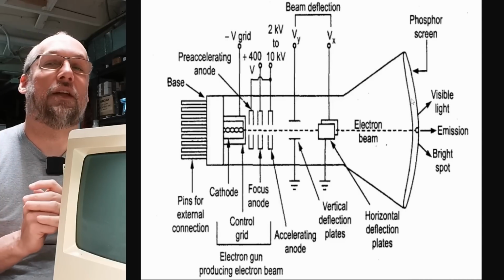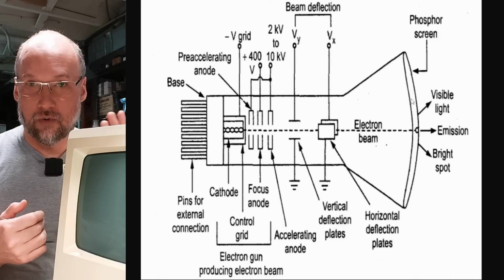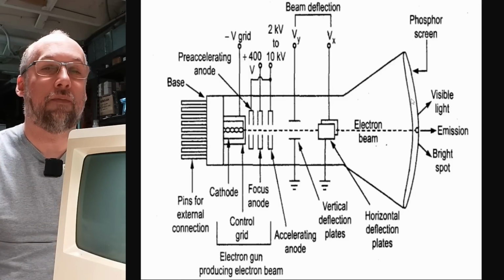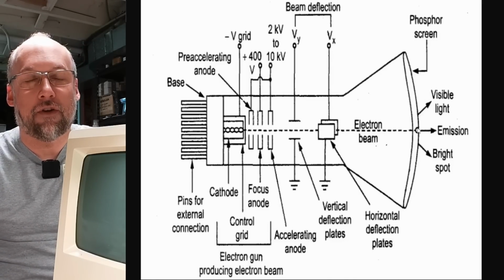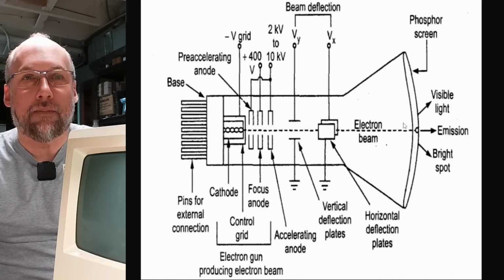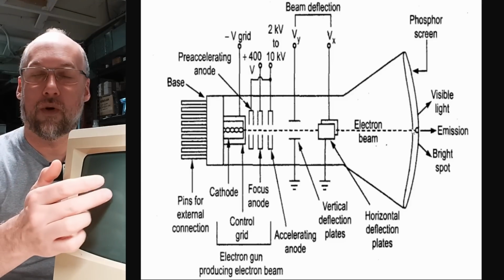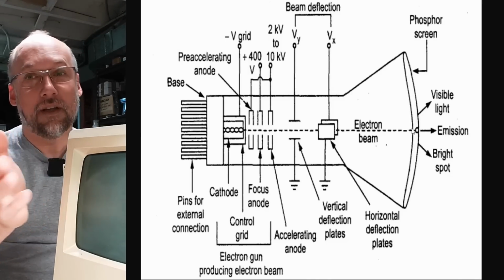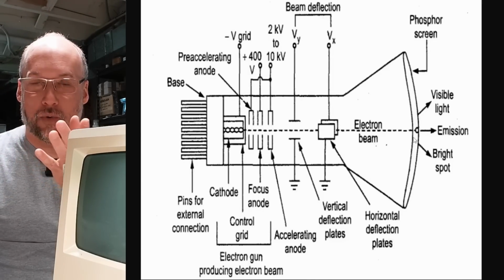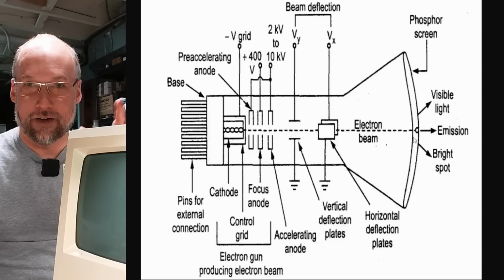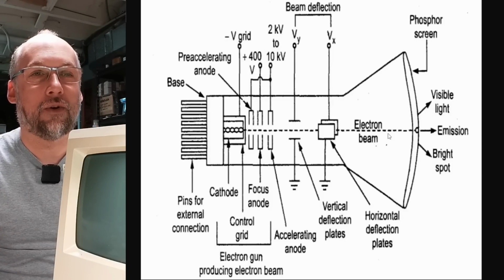The next thing that's essential for generating an image is the high voltage, the 12 to 15,000 volts. We know that's working properly. What that does is it charges the front of the screen with that voltage, and that basically pulls the electrons or accelerates them towards the phosphor, and when they hit the front, they actually glow. We know that that's working because, well, earlier I had the little arc and we tested it with the meter, so that is all good.